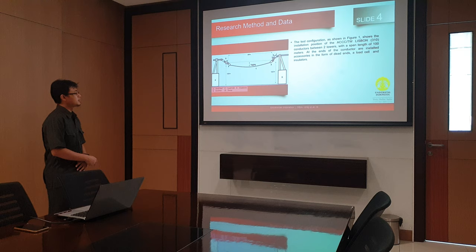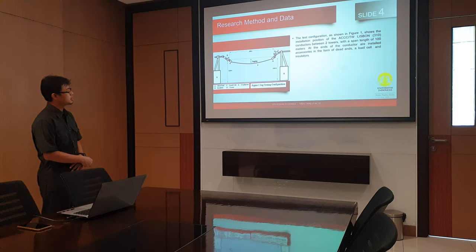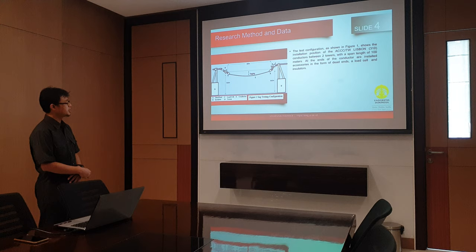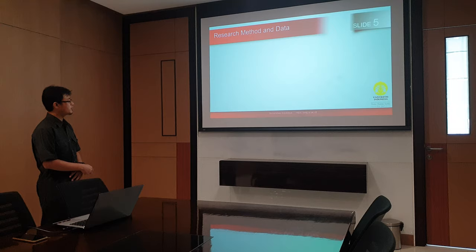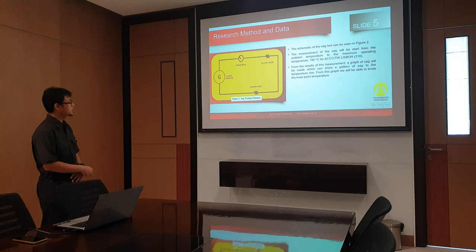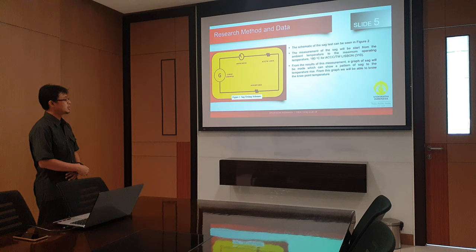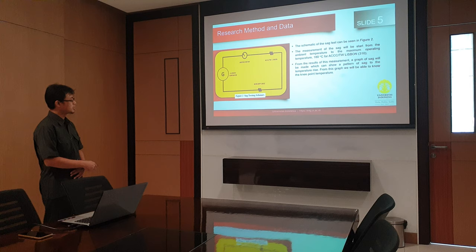In this study, the simulation will be conducted to determine the Knee Point Temperature in aluminum conductor composite core. Research method and data. The installation position of the ACCC conductor is between two towers; the span line is 100 meters. The scheme of the sag test, shown in figure 2, shows the measurement of the sag starting from the ambient temperature until the maximum rating temperature.